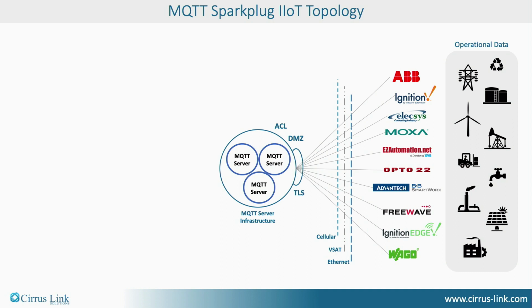These devices are connected, and they're telling the infrastructure about all of their interesting information. Oh, you just changed the pressure transmitter from PSI to kilopascals. Oh, you just changed the flow rate, the orifice plate on a flow computer. Oh, you changed the strapping table on a tank. All that information is feeding into this infrastructure.